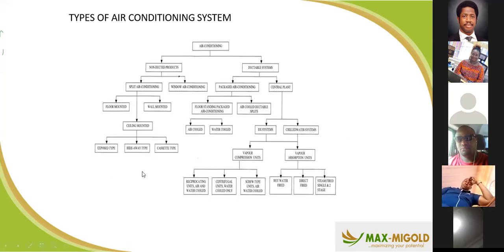Then we have the exposed type, the high wall type, and the cassette type. The cassette type is the fancy type; it goes along with the beauty of your ceiling board. They are very beautiful but expensive. The only issue with the cassette unit is that its drain water has to be discharged through a pump because it sits at a higher level. So if your pump fails, there's a tendency that your ceiling will be dripping water into your office. That's why a lot of people frown at this type. But for fancy and aesthetic sake, some people say they don't want any AC on their wall, everything has to go into the ceiling.